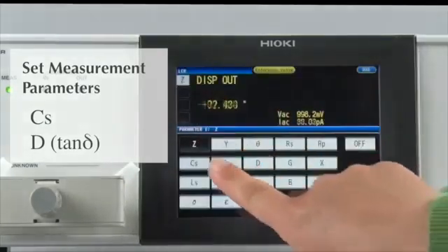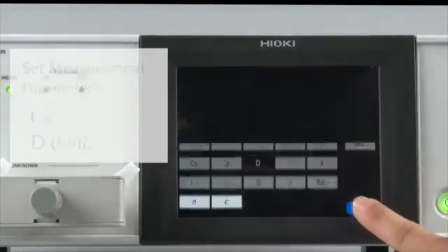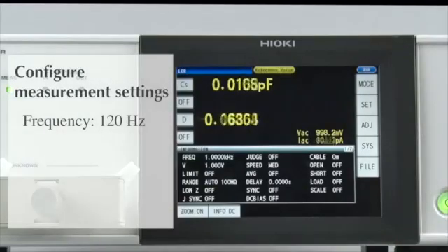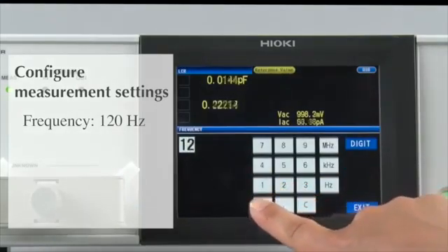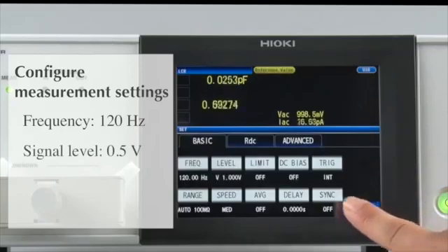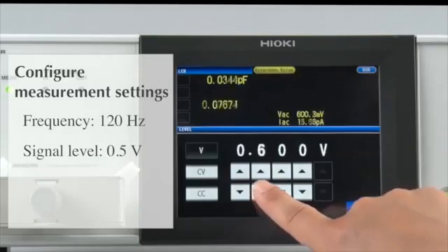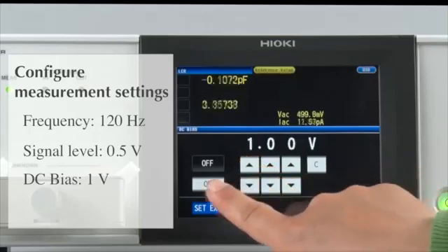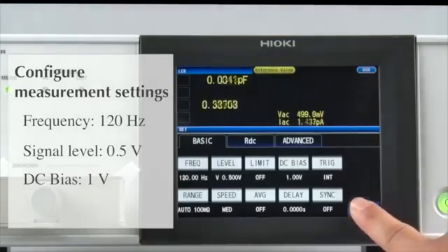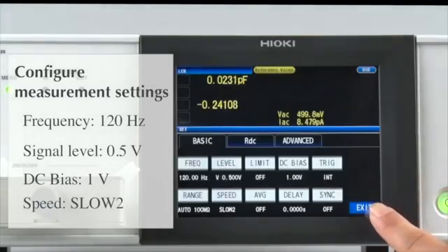Select Cs and D. Then set the measurement frequency to 120 Hz. Configure the measurement signal to 0.5 volts. Set the DC bias to 1 volt. By selecting Slow 2 as the measurement speed, you can achieve more stable measurements.